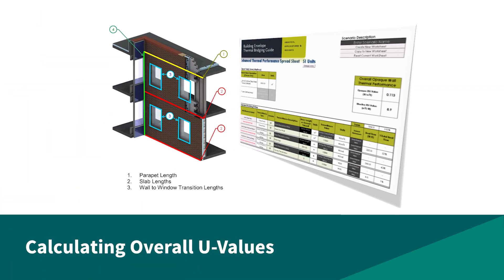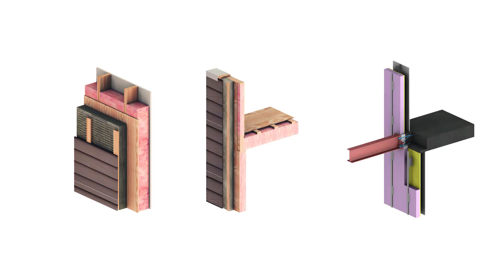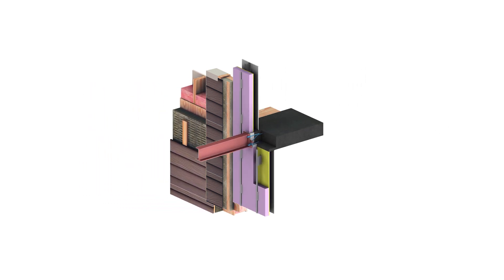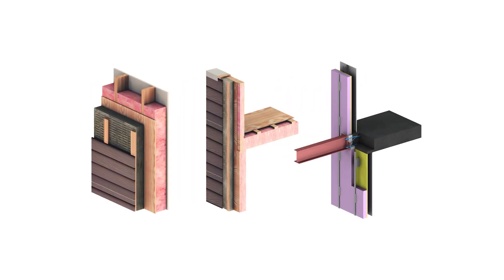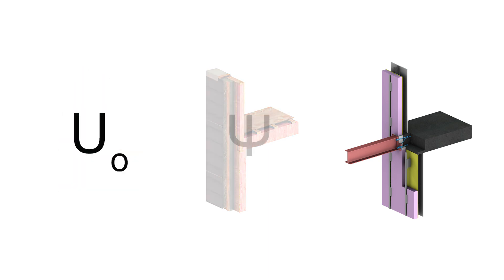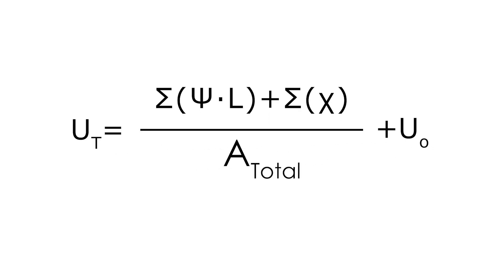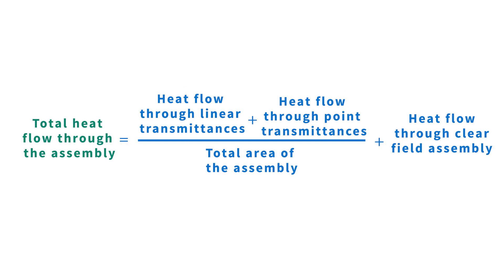Calculating overall U values. With these three types of thermal transmittances — clear field, linear, and point — we can now calculate the overall assembly U value that includes all the impacts of thermal bridging. Since the performance of these details have been calculated separately as the clear field U value, the psi value, and the chi value, the heat loss they create can be simply added together. Therefore, the overall assembly U value can be calculated using this equation. In essence, the total heat flow through the assembly is equal to the heat flow through the linear and point transmittances divided by the total area of the assembly, plus the heat flow through the clear field portions of that assembly.